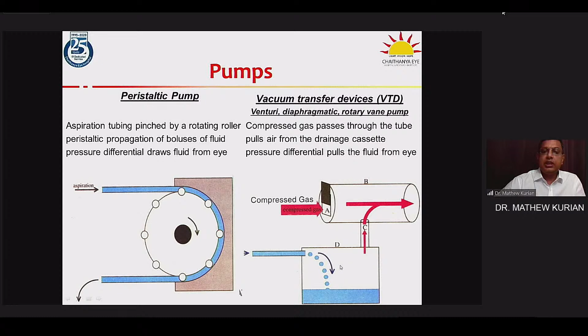In vacuum transfer devices, the compressed gas passed through a tube in this Venturi model, and this created a pressure differential in the drainage cassette, drawing the fluid from the eye through the aspiration line in an attempt to negate the pressure differential.